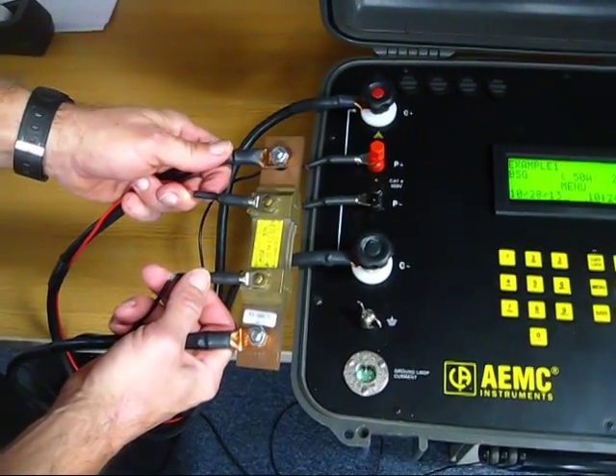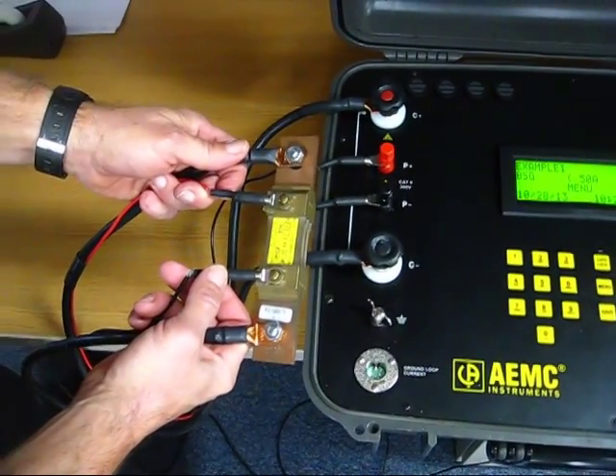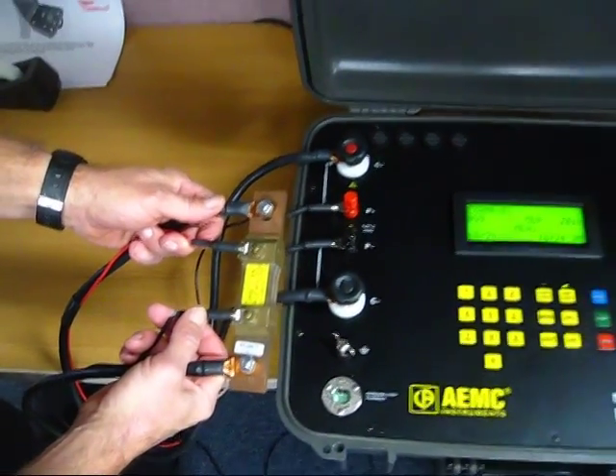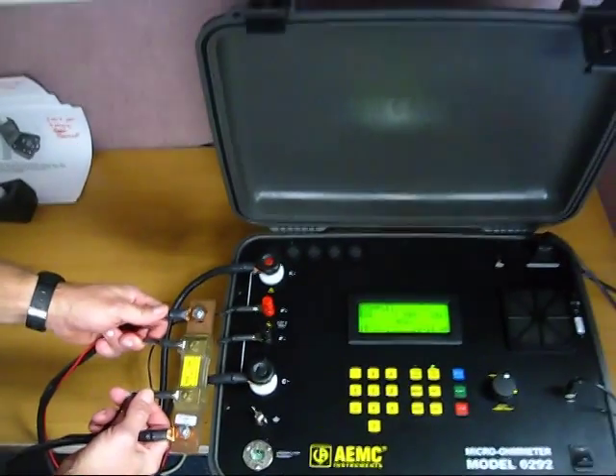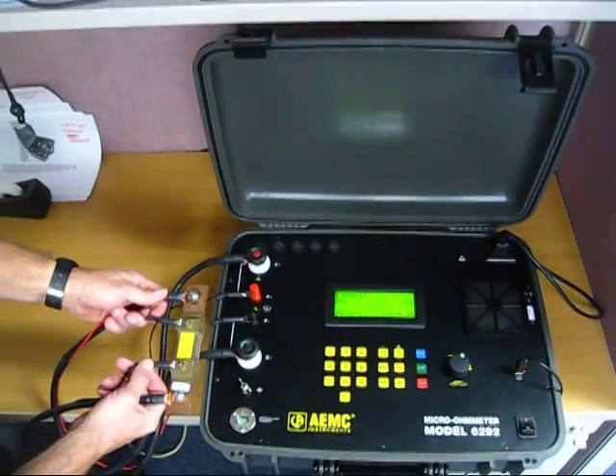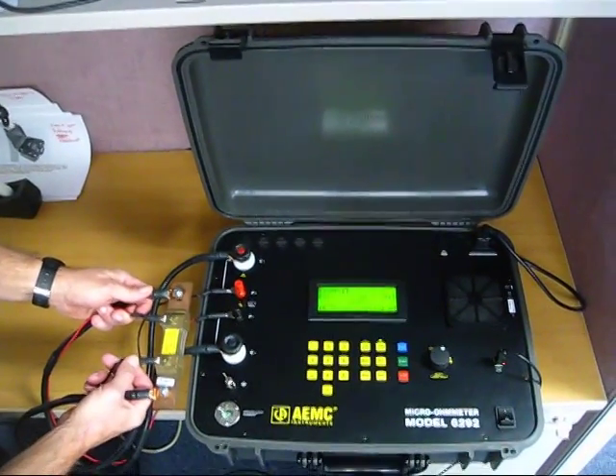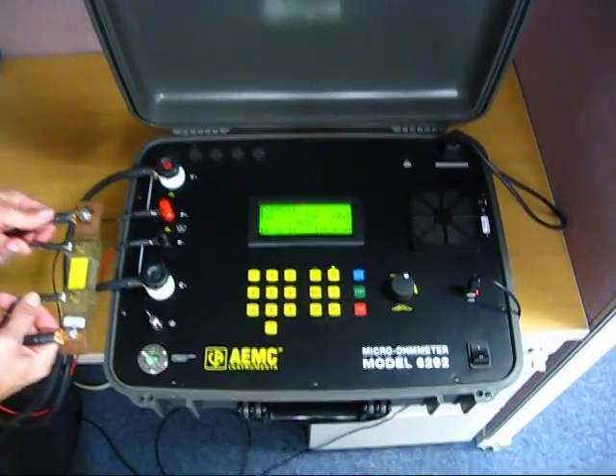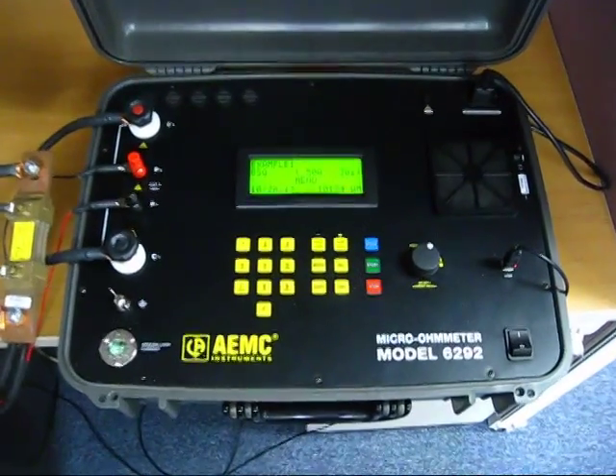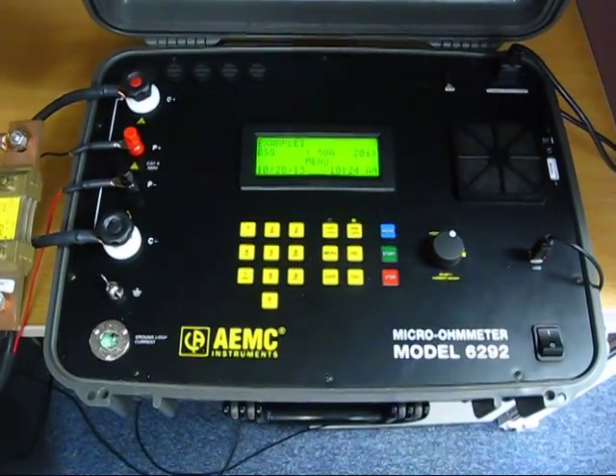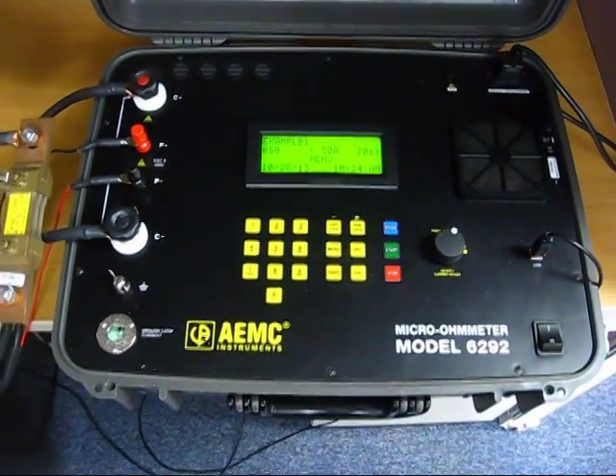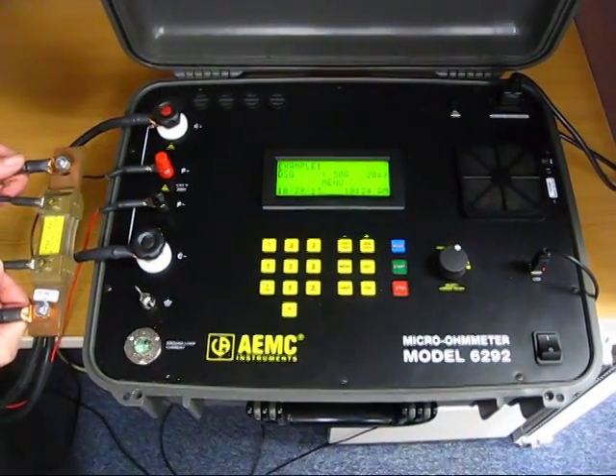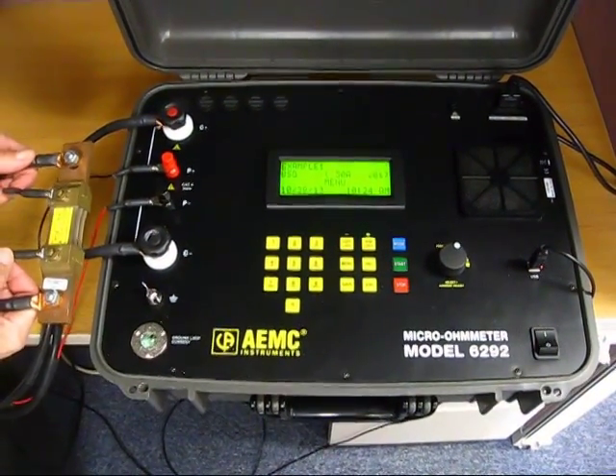For this test, we will run a 20-second test in normal mode with a current of 50 amps. During this test, we will take partial measurements at 5-second intervals and store the results in the instrument's internal memory.